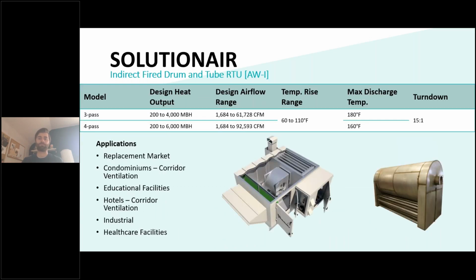one of our suppliers. So looking at the drum and tube product, we can go up to 60,000 CFM with a 3-pass model or 90,000 CFM with a 4-pass model. The only difference between those really is the number of times the products of combustion pass through that heat exchanger. It's very easy to identify if you have a 3-pass or a 4-pass model. With the 3-pass, your stack is going to be on the opposite side from your gas controls, and on a 4-pass, it'll be on the same side. In addition to that, all of those units are a 15-to-1 turndown ratio, a temp rise between 60 and 110 Fahrenheit, and a max discharge of 180 for the 3-pass or 160 for the 4-pass.